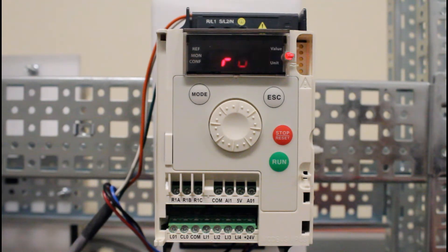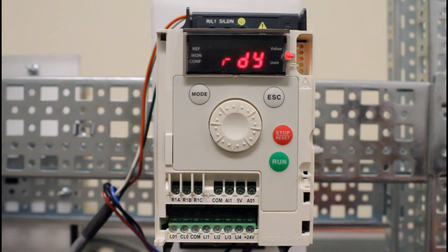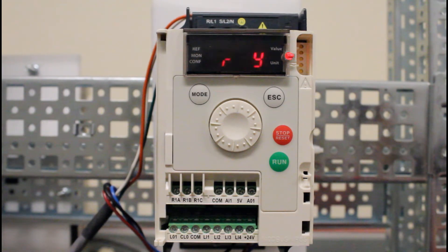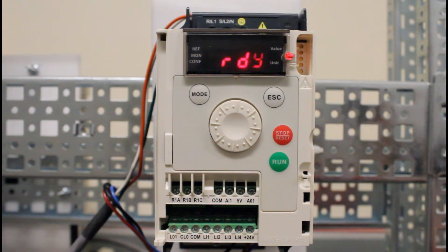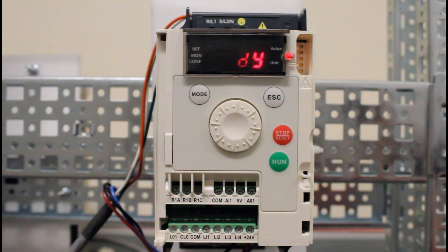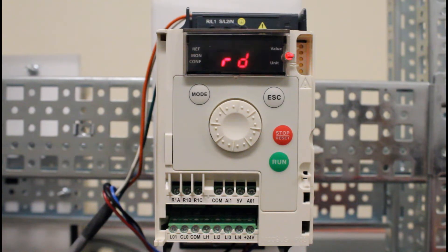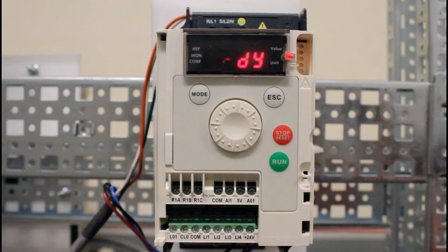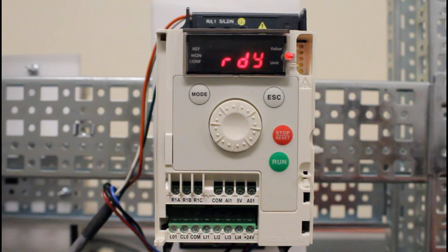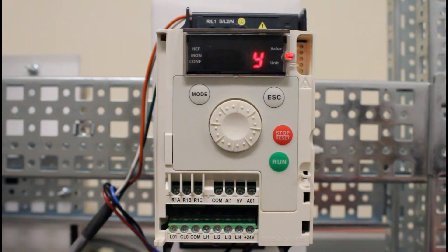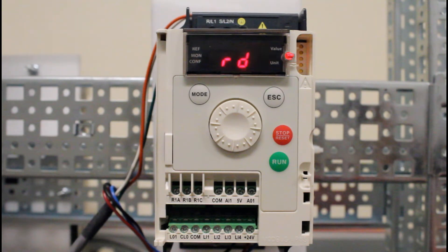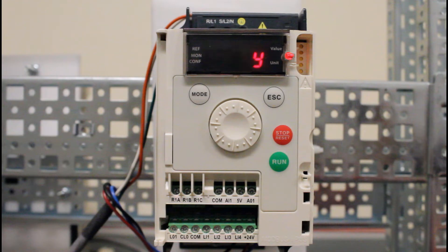The third condition is that the fault itself has to be able to be cleared by the drive. Some faults cannot be cleared automatically, some require powering down like a short circuit, but most all of them like any kind of power blips will let you attempt to restart again.